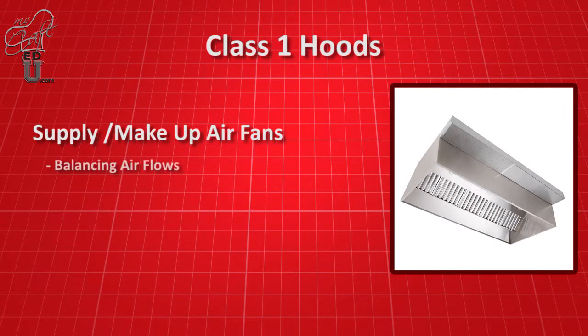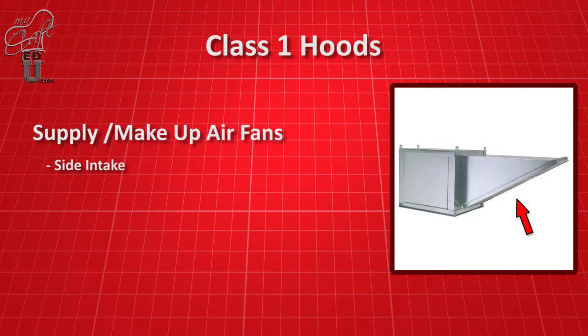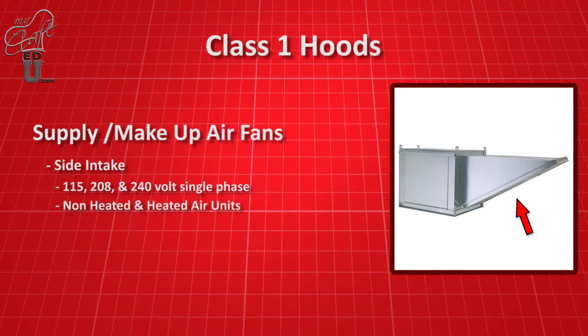In addition, supply fans assist in the balancing of airflows to prevent building pressure-related problems as well as utility savings. Makeup air fans typically have a side intake and are required by code to be at least 10 feet away from the exhaust fan to prohibit grease-laden air from exiting the exhaust fan from re-entering the building through the makeup air fan. Makeup air fans are available in 115, 208, and 240-volt single-phase and in non-heated and heated makeup air units for colder climates. This simply means the outside air is tempered or heated as it passes through the supply duct before entering the plenum.